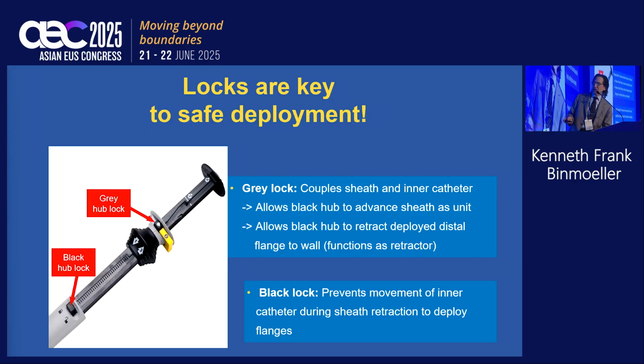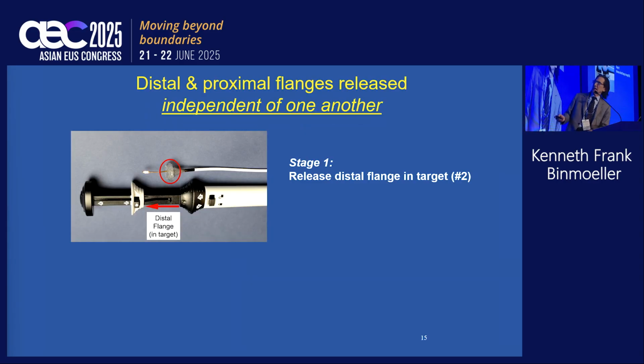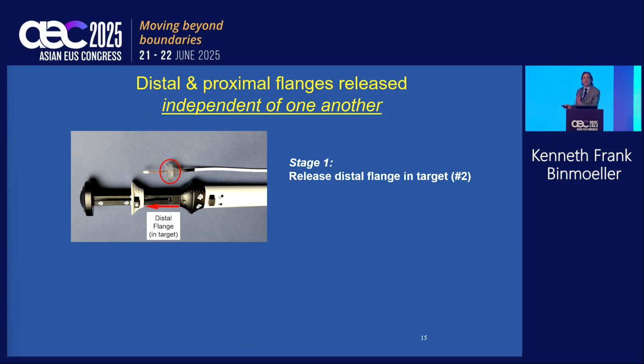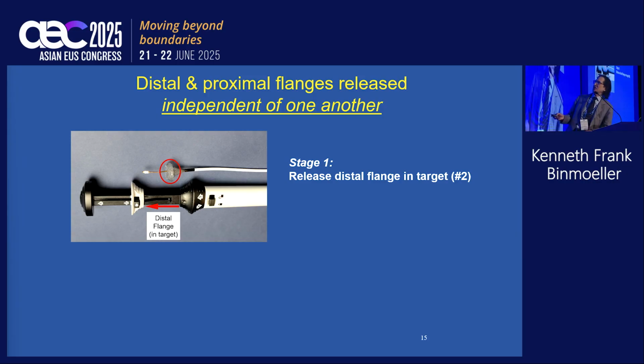So again, the locks: black hub lock, gray hub lock. You need to know where they are, and we even added icons here so that you know what's locked and what's unlocked. The distal and proximal flanges are released independent of one another, and that is critical. You do not want to accidentally deploy the entire lumen-apposing stent inside of your target. Stage 1, you release the distal flange in your target. So that's number 2. See the number 2 here? You have pulled this gray hub up to release the distal flange in your target. There it is, it's released. This is the runway for the release. This is the tray that houses the distal flange. This is the nose cone here.